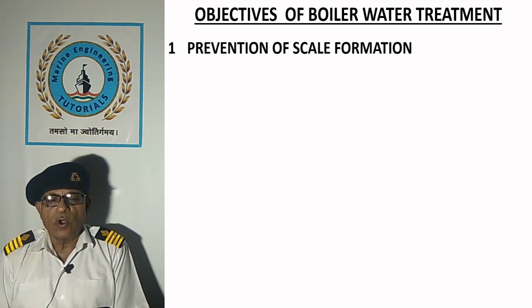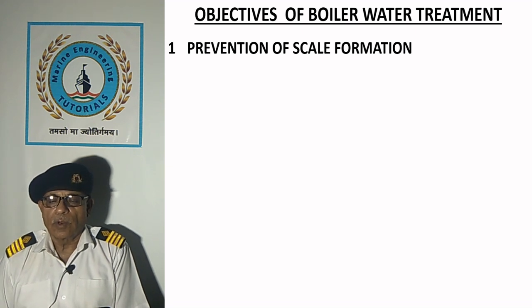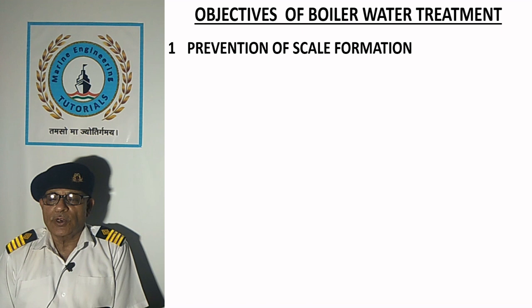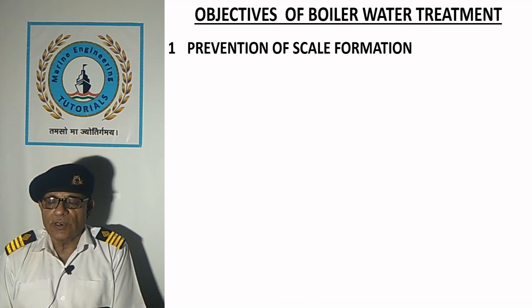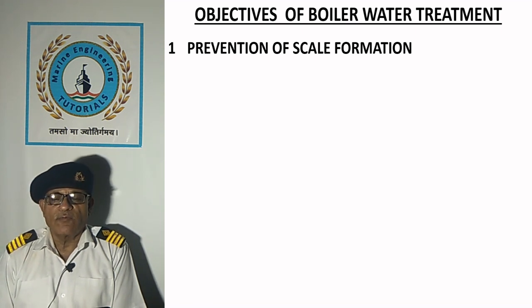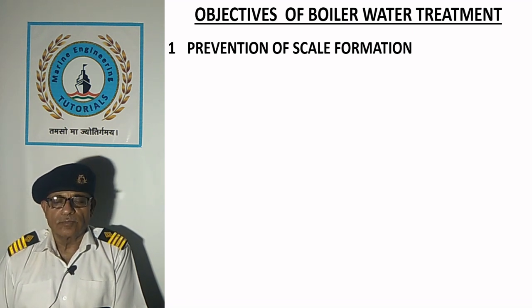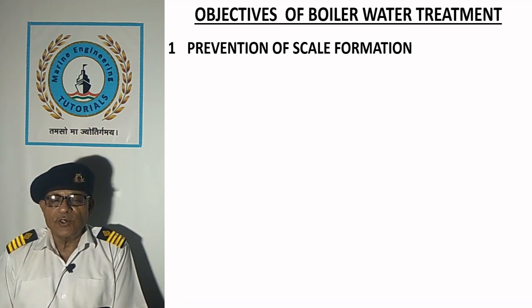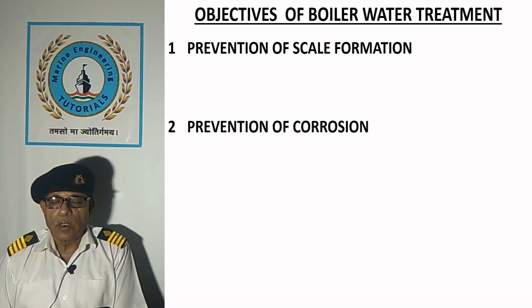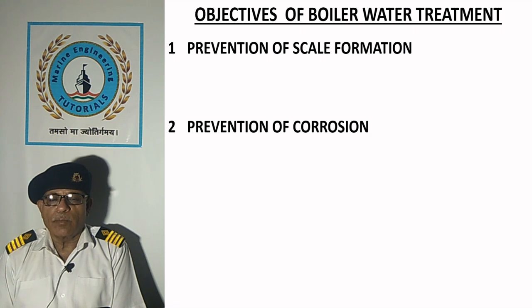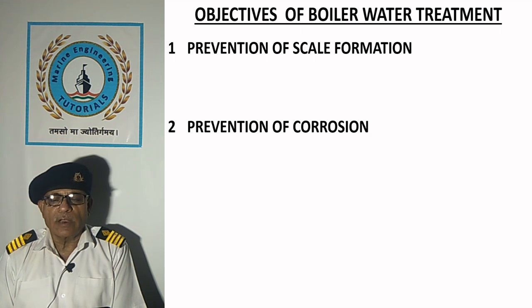First is prevention of scale formation — prevention of scale formation in the boiler and feed system by using distilled water or precipitating all scale-forming salts into non-adherent sludge. Second is prevention of corrosion — prevention of corrosion in the boiler and feed system by maintaining the boiler water in an alkaline condition, free from dissolved gases.